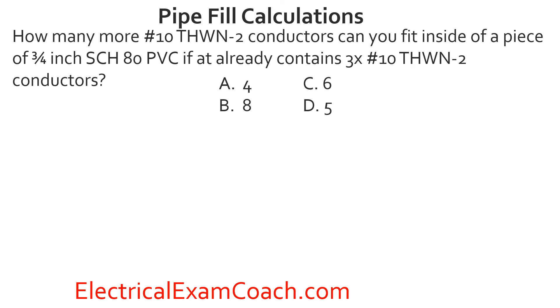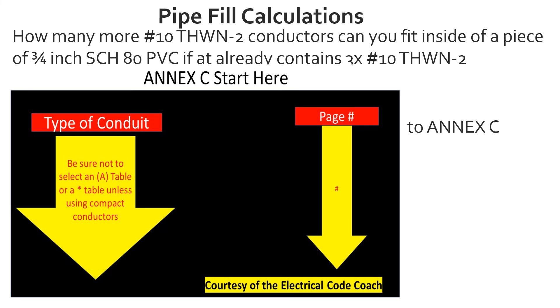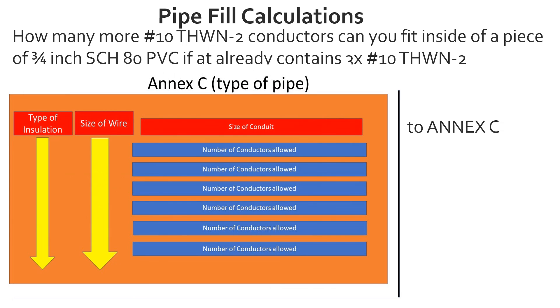Practice problem: How many more number 10 THWN-2 conductors can you fit inside a piece of 3/4-inch schedule 80 PVC that already contains three number 10 THWN-2 conductors? Are they all the same size and insulation? Yes. Head to Annex C, find schedule 80 PVC on the left — not the A version — cross over to the page number. Read the black bold heading, find THWN-2 insulation, find size 10 wire, come across the top to 3/4-inch conduit, and tee off. The starting value is 7. Minus the 3 already in the pipe, we can fit 4 more.